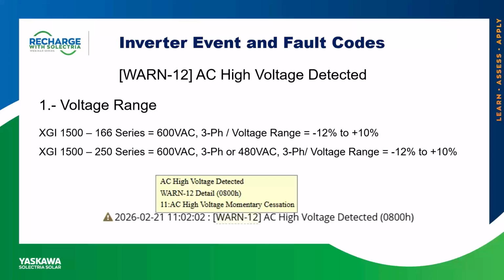As for the XGI 1500 250 series, for the 480 volt AC option, that would be 528. When the unit has grid connected, it can go up to 528 volts AC. Now, it's important, we never want to go above either 660 volts AC or 528 volts AC. If we do, we're going to get this Warn 12 high AC voltage detected fault, and that may result in damaging the inverter.